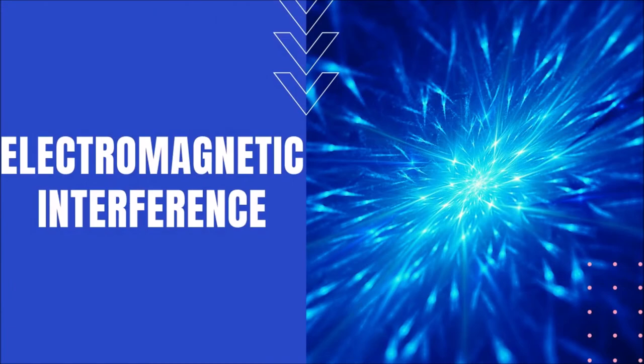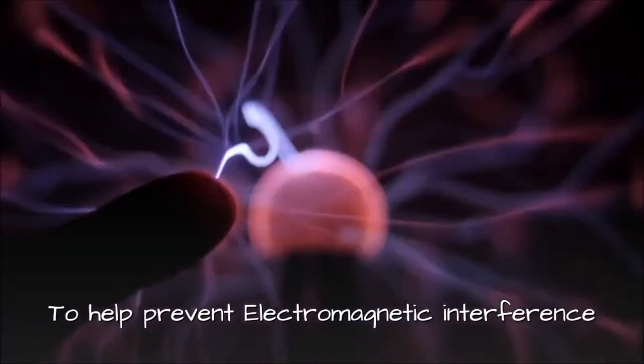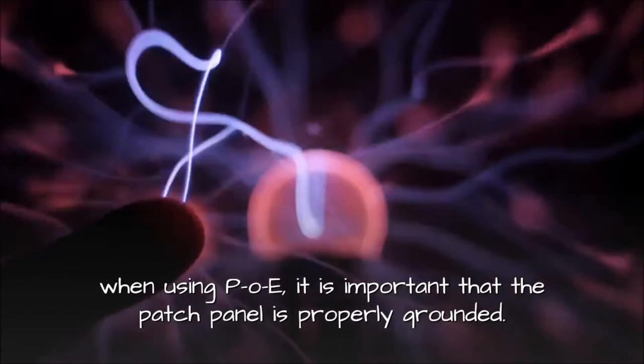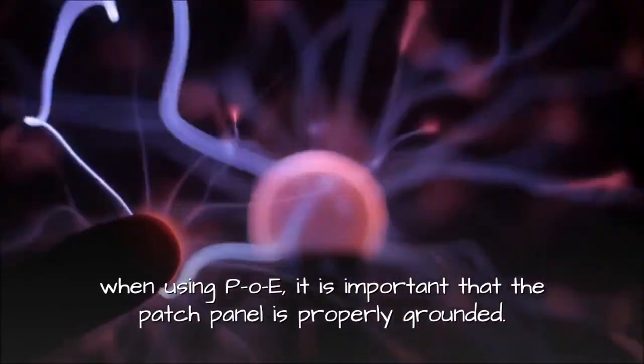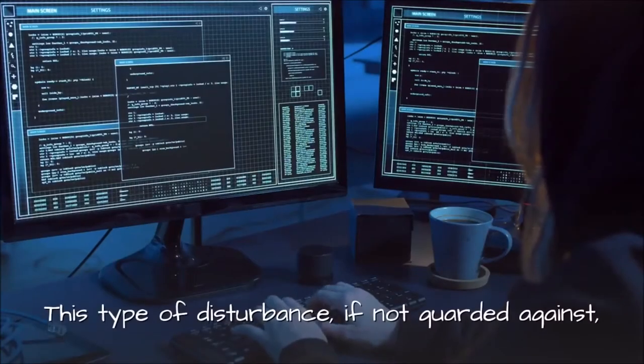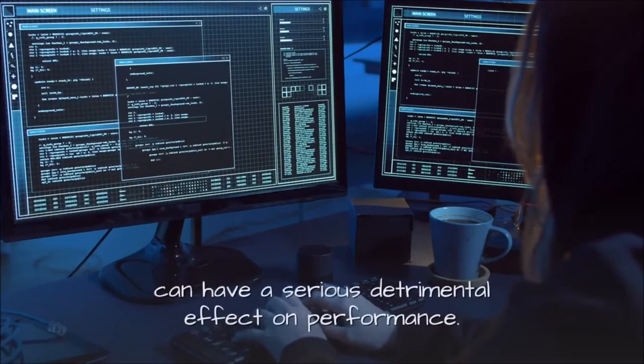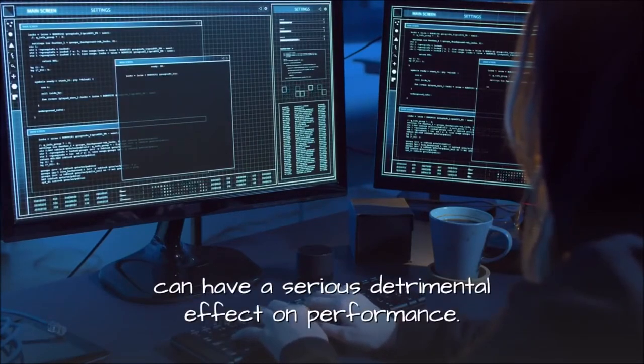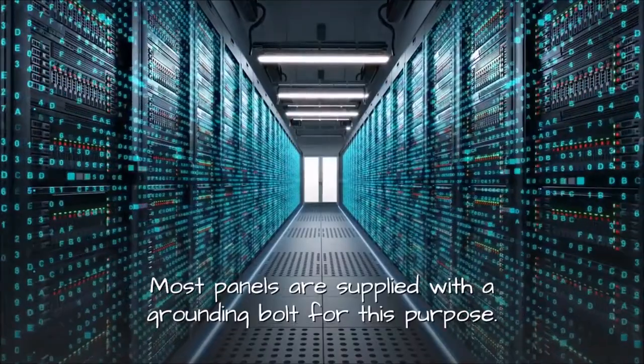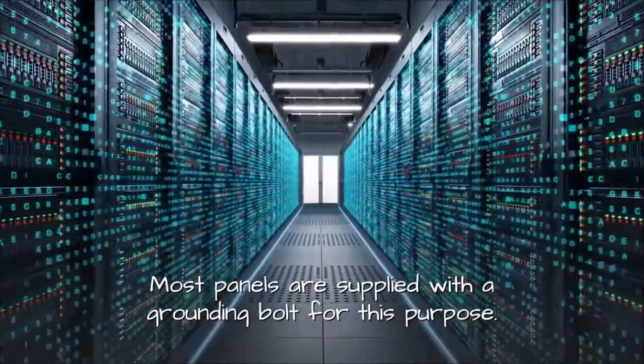Electromagnetic interference. To help prevent electromagnetic interference when using PoE, it is important that the patch panel is properly grounded. This type of disturbance, if not guarded against, can have a serious detrimental effect on performance. Most panels are supplied with a grounding bolt for this purpose.